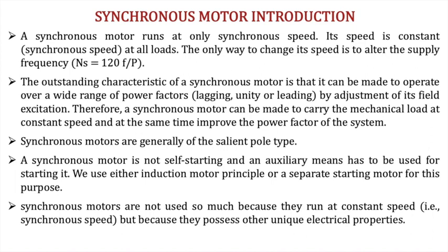A synchronous motor basically runs at only one speed, that is the synchronous speed given by 120 f by P, but it can be made to operate over a large variety of power factors, from lagging power factor to unity to leading power factor, just by changing the field excitation. Therefore, the synchronous motor can carry the mechanical load at constant speed, but at the same time improve the power factor of the system. And when it is made to improve the power factor of the system, it is known as a synchronous condenser.